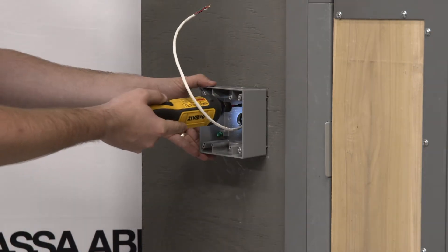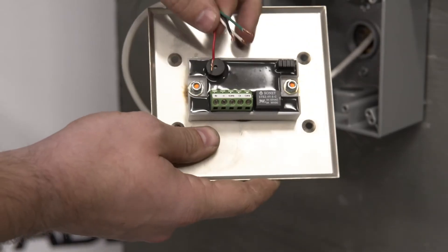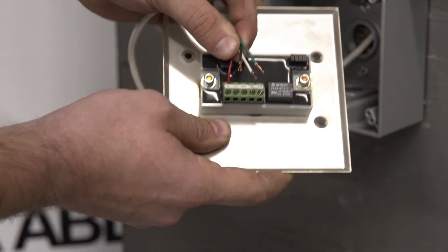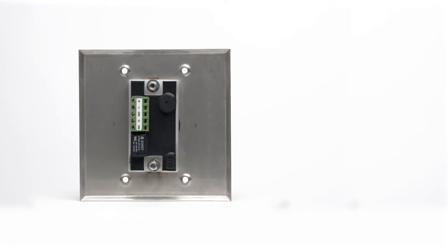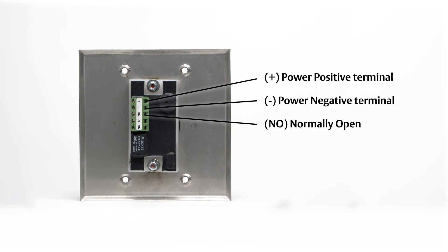To ensure the proper wiring connection, loosen the screws fully and note the silver contact is all the way down. Insert one wire into each of the following terminals: the power positive terminal, the power negative terminal, the normally open or NO terminal, and the common or C terminal.